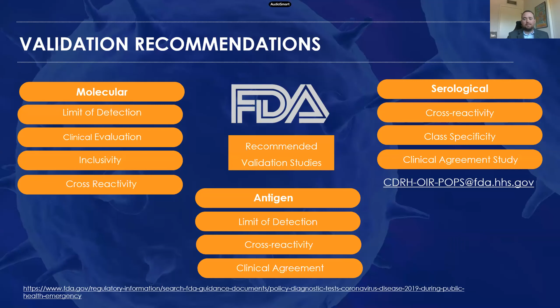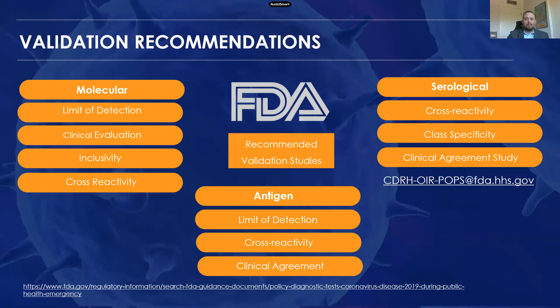FDA recommends that human specimens from microbiologically confirmed cases of COVID-19, meaning an RT-PCR assay, should be used for validation of serological type tests. Now, recently, there's been a lot of scrutiny over serological tests that have gone through a certain pathway that hasn't had FDA review of their performance. So FDA, to kind of quell some of the concern about this that's been emanating in the public, has partnered with NIH, CDC, and BARDA to provide positive sera and negative sera and make that available to manufacturers in order to validate their serological test. This is a voluntary program, and you can get more information on this program at the CDRH OIR POPS email address on this slide. More details are forthcoming, but right now the agency is asking that you engage them in discussion to get information on this pathway.